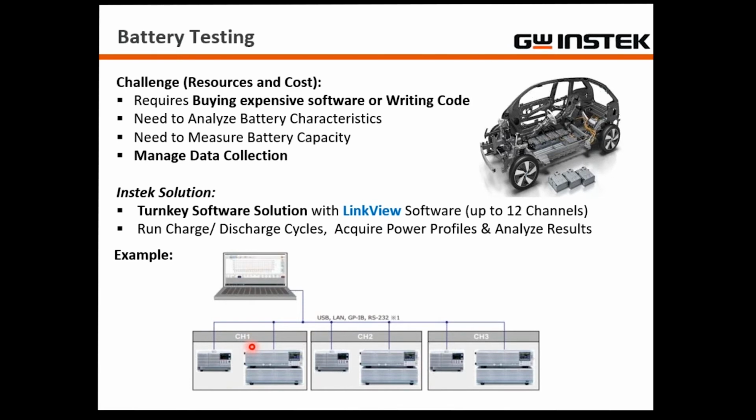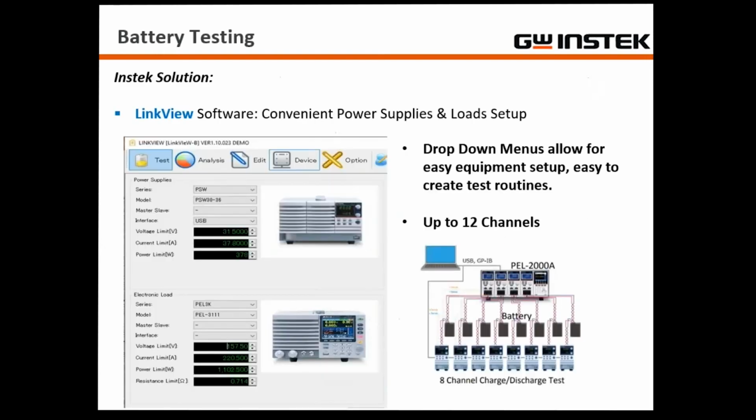However, what we're trying to really get people to know is our LinkView software. With applicable e-loads and power supplies, you can actually control up to 12 channels on one terminal using our software. We can run the charge and discharge cycles, acquire the power profiles and analyze the results. It's very easy, well, in my opinion, very easy to navigate through. It's very intuitive. Obviously, we always recommend that you read the manual for the software, but once you get the hang of it, it's very easy to program.